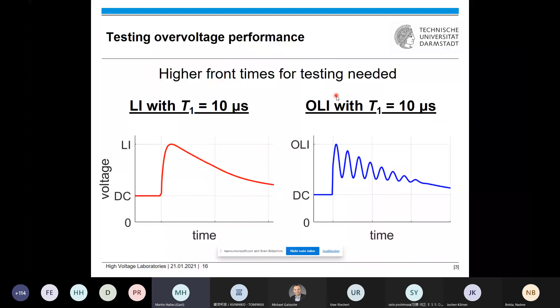Both solutions are possible in general, but when you now look at the technical details for a generator with a lightning impulse and for an oscillating impulse, you will see that the charging energy is 270 kilojoule for a lightning impulse generator for our technical ratings, while OLI would just need 30 kilojoule. The charging voltage is quite much more, 1.8 to 1.2 megavolt, and also the height and the weight of such a generator is much higher. So you see also OLI is a very efficient solution to test the overvoltage performance of this large GIL assembly.